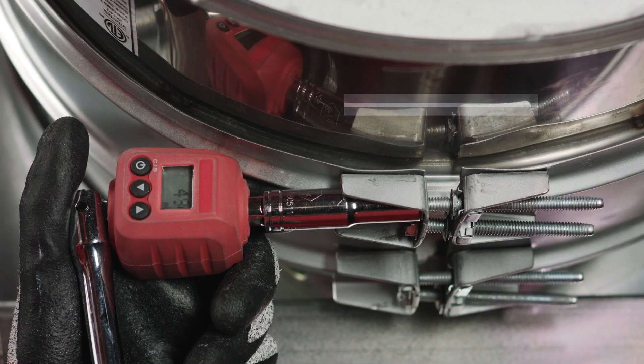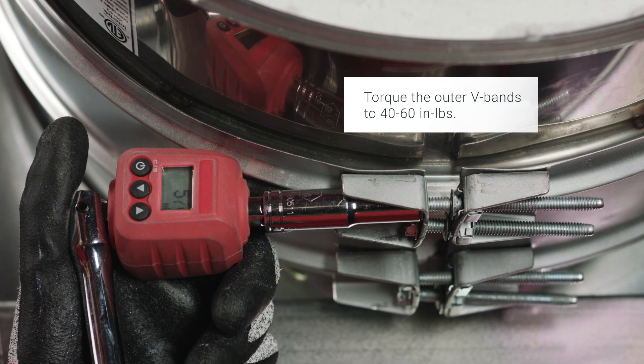Tighten the quarter 20 hardware between 40 and 60 inch-pounds. Smooth and remove any excess sealant from the inside of the duct surface to prevent grease buildup.